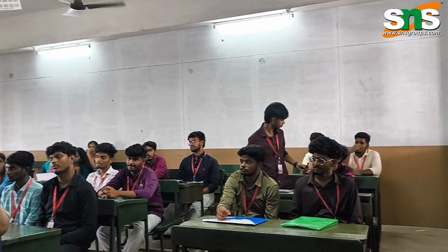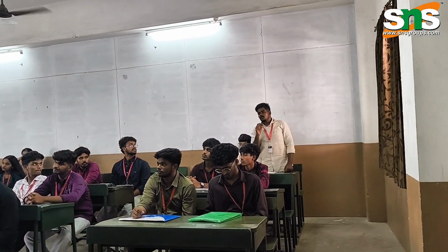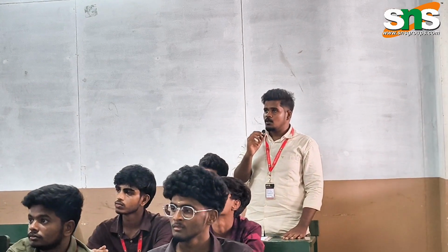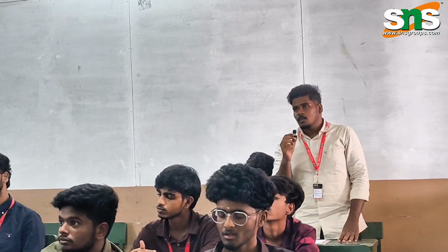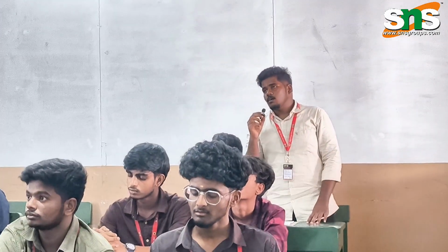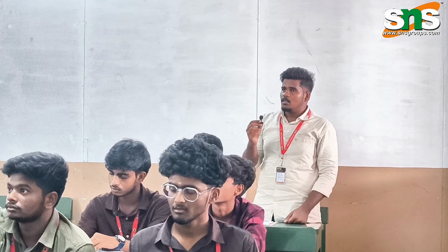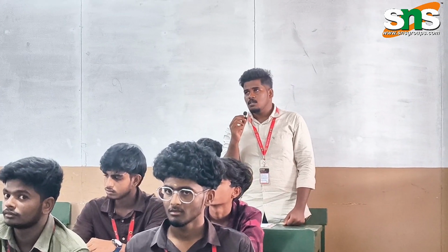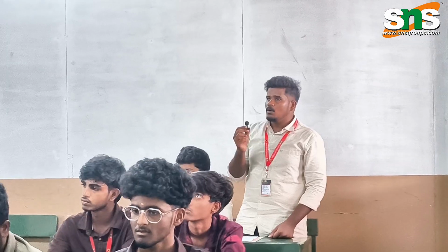Okay. Finally, who's going to conclude? The conclusion: this case study explained how circuit breaker trip failure damaged an industrial transformer. The failure allowed fault current to flow continuously through the transformer winding. Excessive heating caused insulation damage, coil contamination, and system shutdown.